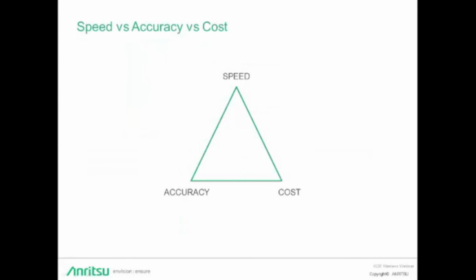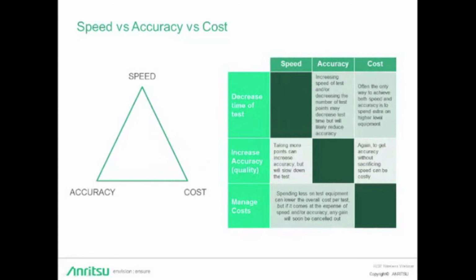Before jumping straight into faster test times, though, it's important to understand the trade-offs. Generally, you have three forces working against each other: speed, accuracy, and cost. So speeding up measurements is usually done in one of two ways, either taking fewer points or taking the same number of measurements in a shorter amount of time. The former method will decrease consistency and/or accuracy of your test and diminish quality, but the latter is generally only achieved with more expensive equipment.